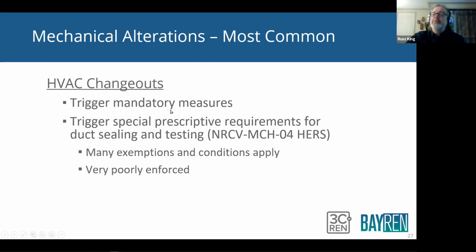So HVAC changeouts trigger mandatory measures and they trigger special prescriptive requirements for duct sealing and testing. The form that's filled out for those duct sealing and testing is the NRCC-MECH-04-HERS, the NRCV for verification. There are many exemptions and conditions that apply. And unfortunately, this is very poorly enforced. There are a lot of these types of projects going on, HVAC changeouts in commercial buildings, strip malls, office buildings constantly getting package units replaced, and the ducts aren't getting tested. So I hope building departments will take note of this and realize that there are requirements for testing and sealing of ducts. And hopefully we'll start enforcing that a little bit better.